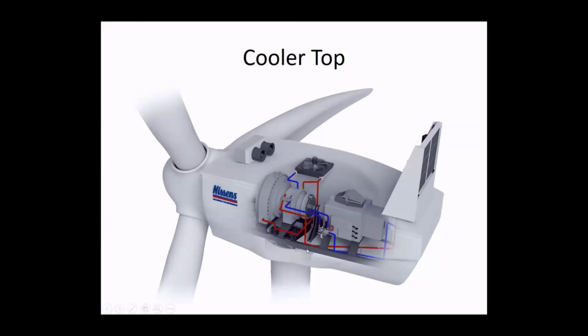So if you see these particular pipes inside, they circulate a liquid that is 50% glycol and 50% water. Glycol is used instead of plain water because wind turbines can be mounted in icy or snowy conditions where there is more wind. In such places, if you use plain water inside these tubes, it gets frozen and there won't be any water circulation for heat removal.